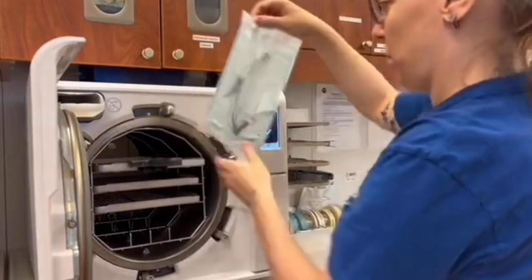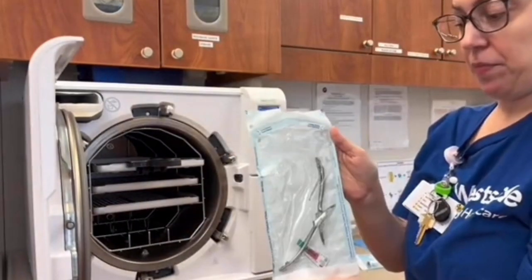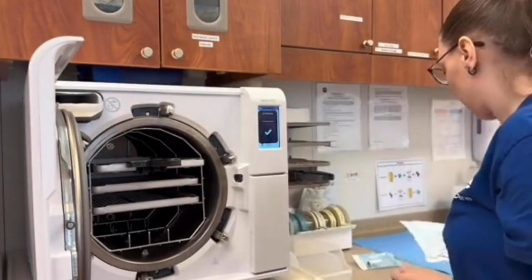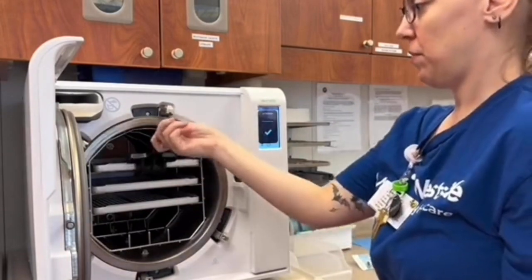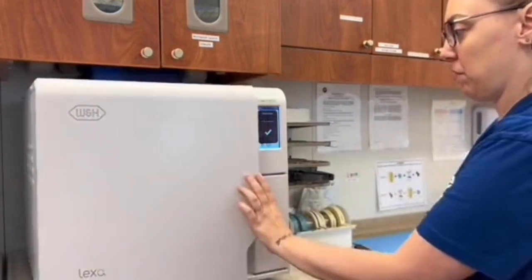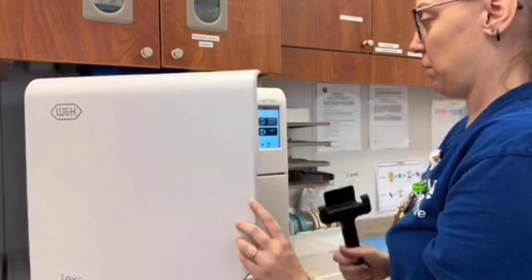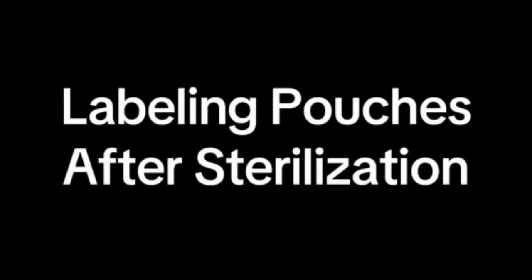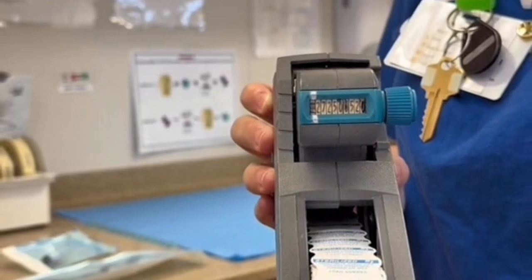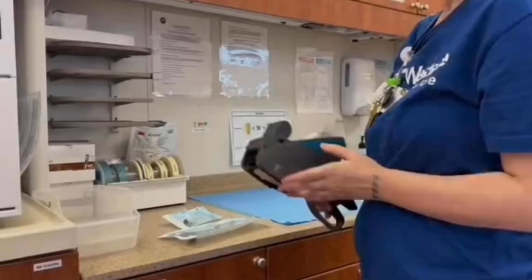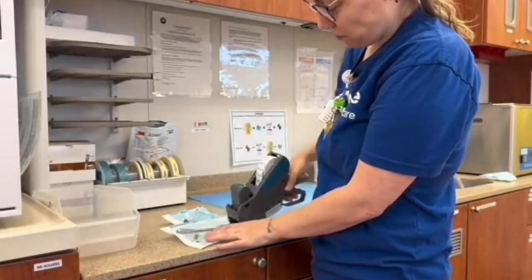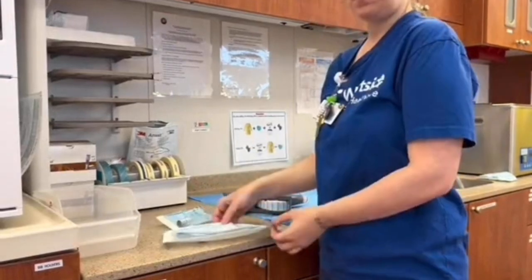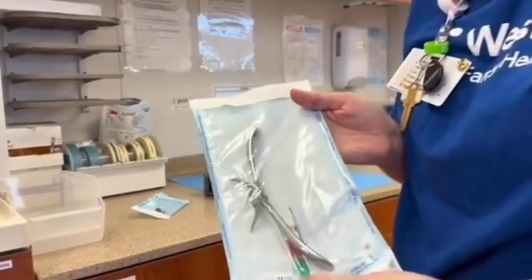If any indicator didn't work or there is moisture in the pouch, put it in a new pouch with a chemical indicator and sterilize it again. You don't need to clean it again before doing this. Put a label with the load number and the date on the clear side of each pouch. You could find the load number on the screen of the autoclave.